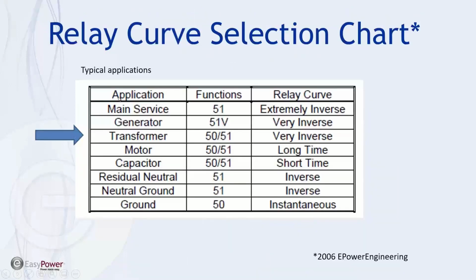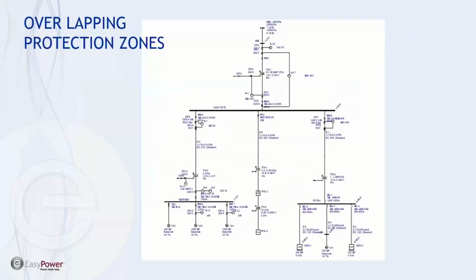Now, there are several curve profiles that are available on any manufacturer's relay data sheet. And so this is something I copied from a website that recommends, basically for transformer protection, that we want to use a very inverse curve. Now, this is, again, not set in stone. It's just a guideline or a starting point for doing your coordination setup.